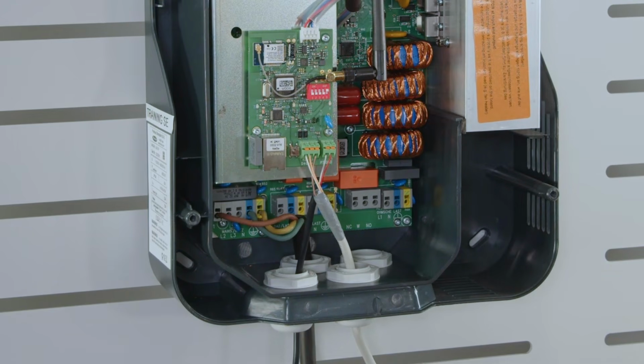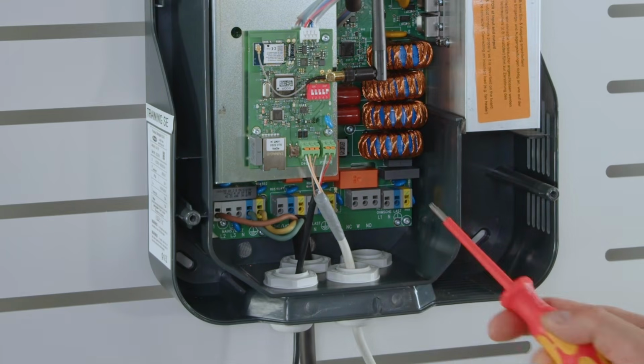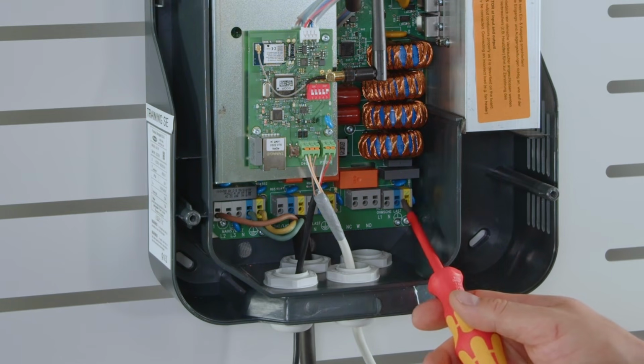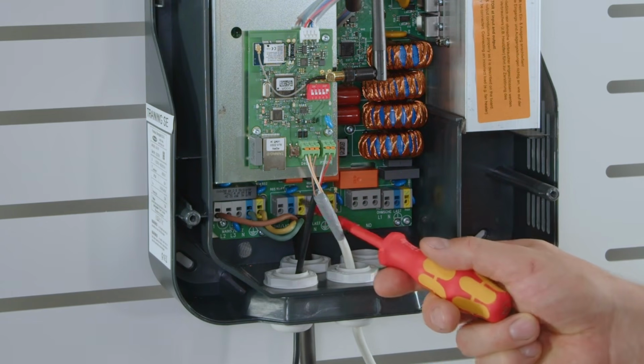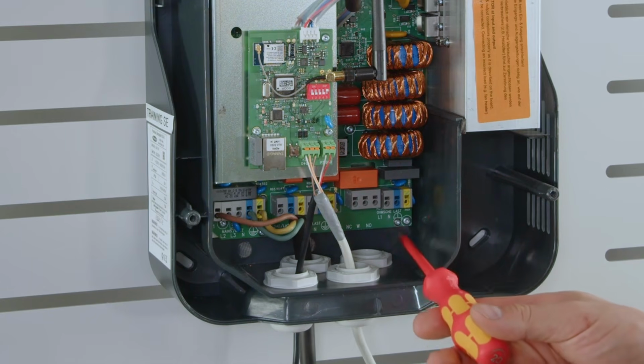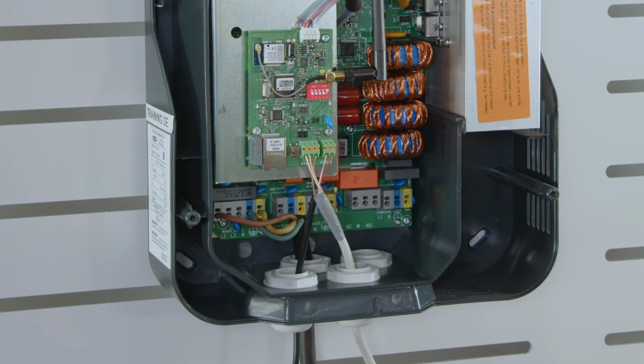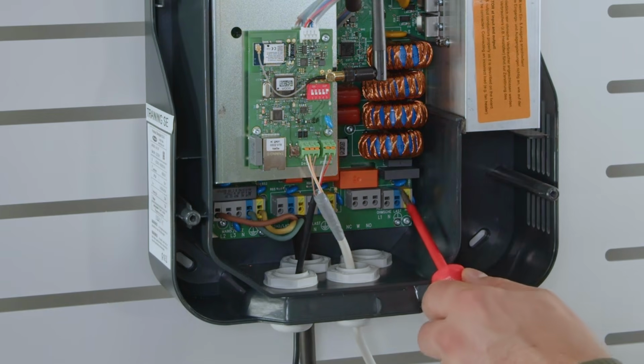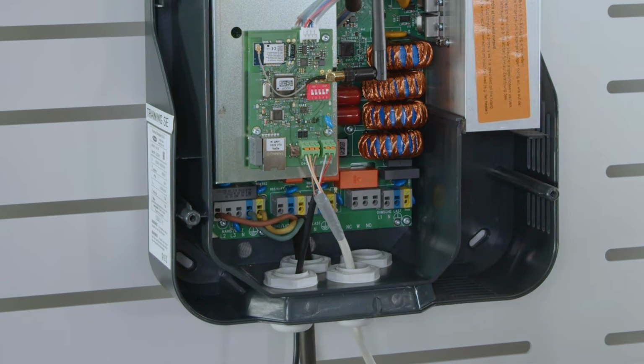Single or three phase, respectively, depending on what you're using as heating rod, if it's a single or three phase heating rod. And then for the heating rod connection, we start at the very right with L1, L2 and L3. And please don't forget, only L1 is the dynamically controlled one. So if you have only one heating rod in a single phase that you want to connect, it has to be connected to this one, as this one is the regulated one. Phase 2 and 3 are simply switched on or off. There is no dynamic control.